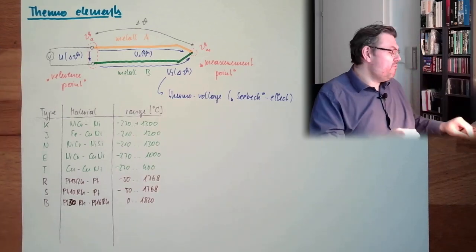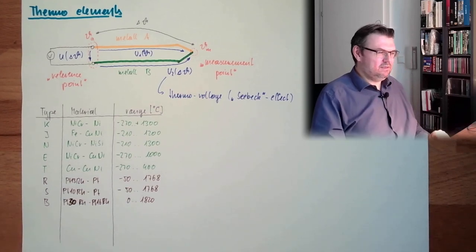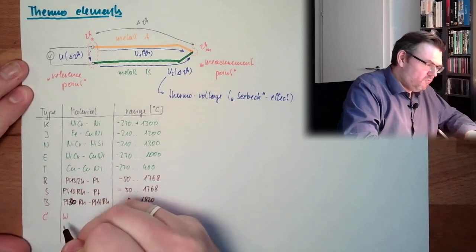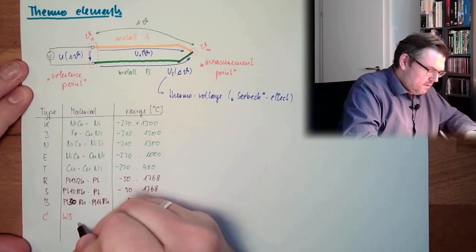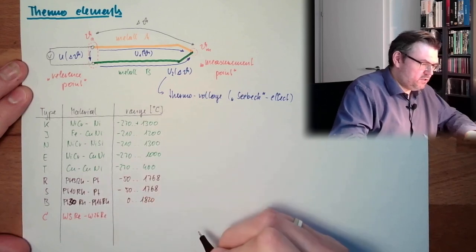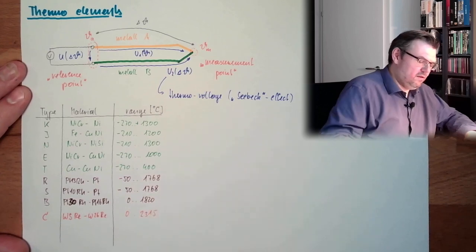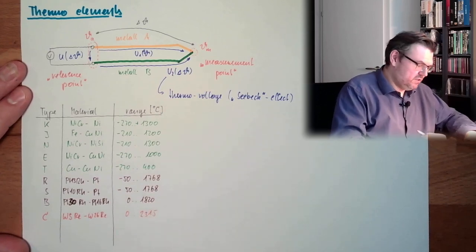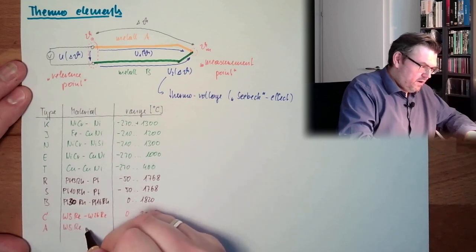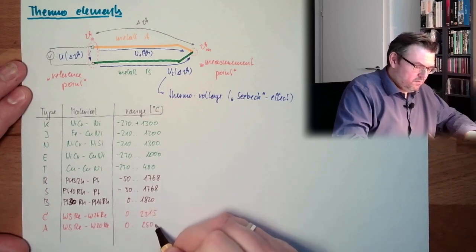And whenever we have really high temperatures, then usually tungsten is somewhere around. So this is type C. This is tungsten, Wolfram is tungsten, rhenium. And this is defined from 0 to 2315 degrees Celsius. Here we measure really high temperatures. And there is also type A, which is tungsten 5 rhenium, tungsten 20 rhenium. This from 0 to 2500.